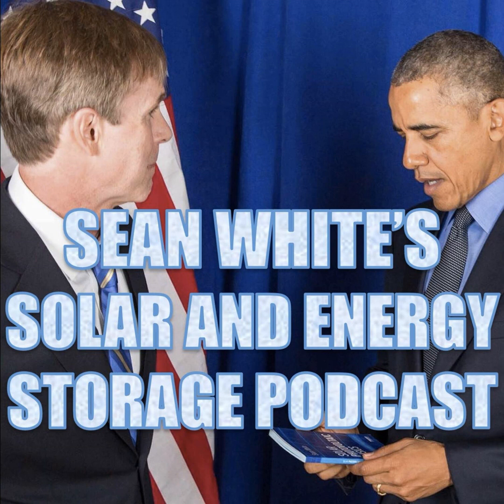And so if somebody had the remote switch, that would be safer than running big cables from your battery to the outside of your house, to the inside of your house, back to the inverter that's sitting next to the battery, for instance. And so if you're connecting a whole bunch of batteries in series here, and you need to be able to have disconnect for sections that are 240 volts or less. Remember, this is not for energy storage systems. So if you have a listed energy storage system that has a voltage that's higher than 240 volts, that's not a problem because you're using Article 706, not Article 480.